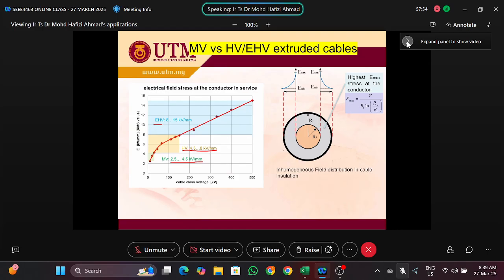Okay, so when we calculate the electric fields, the higher electric field will occur on the surface of the conductor. Okay, so this is the copper conductor, this is XLPE, this is the cable sheath that basically will be grounded, right? Okay, so based on the calculations using analytical method or numerical method, we might see that the higher electric field will be on the surface of the conductor. Okay, and these electric fields should be lesser than the electric strength of the insulation.